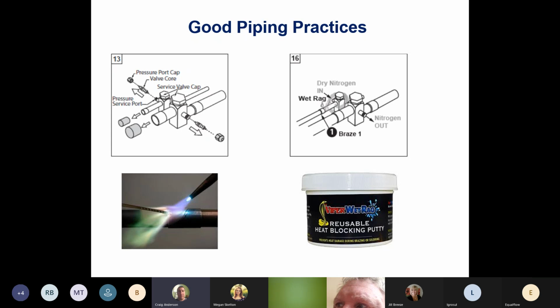Or the stuff here that's in the picture is called heat block. It's about $35, and it should last you about a year. It's reusable. As long as you keep it moist, it will stop any heat going into that service valve. You just take it out of the container and wrap it around your service valves. Much better than a cold cloth. There are demonstrations where people put it on a copper pipe and hold the other end while they heat the other part red hot, and it doesn't get hot on the other side.